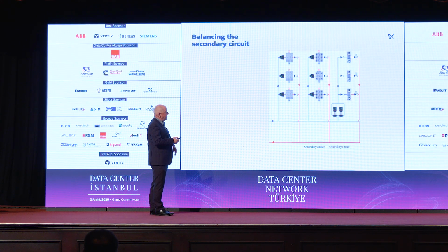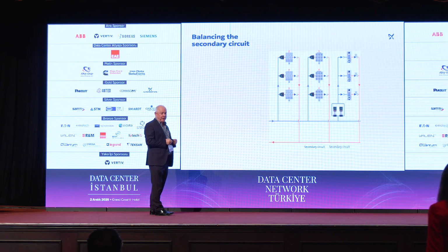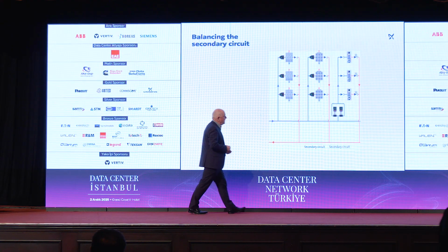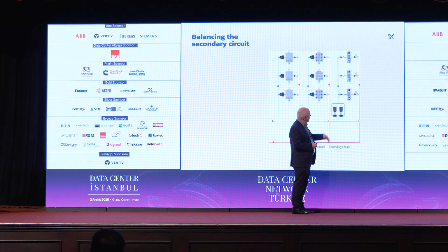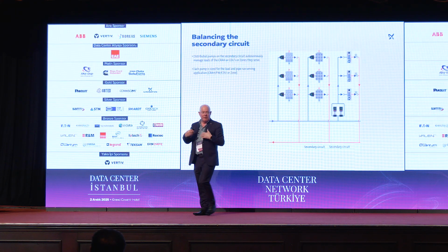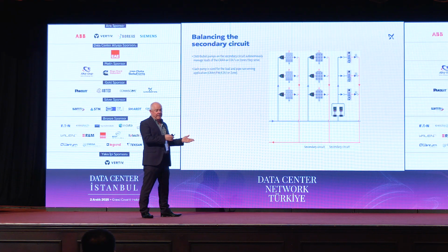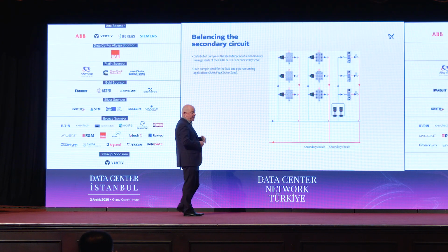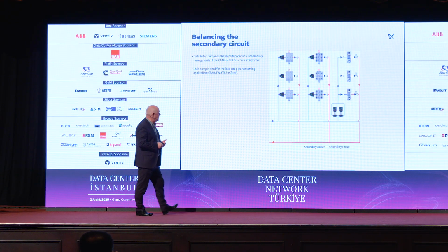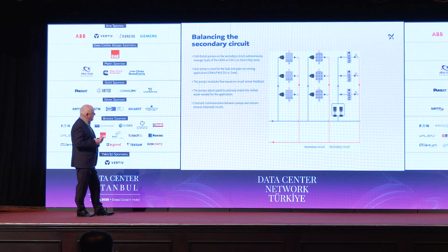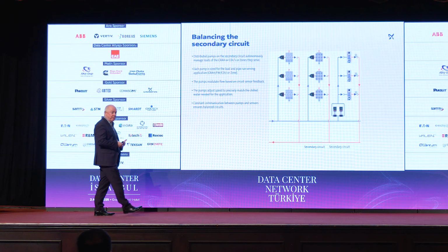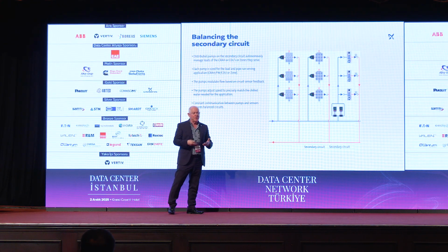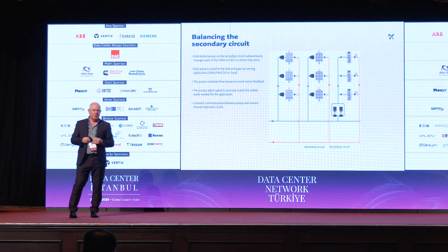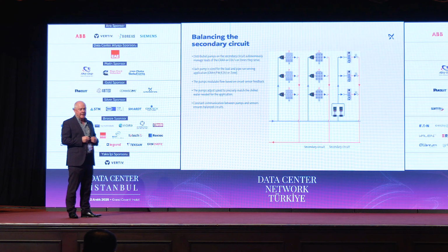So if we look at the secondary side, as I said, there's a pump on each load, which is providing the right amount of cooling. And we can see here where we've got a zoned load where we've got one pump pumping up to various different loads. And we can mix and match different kinds of cooling. So we can have fan walls, we can have CRAH units, we can have liquid cooling, all on the system. It doesn't really matter to the individual pumps what the load is. They're getting sensor feedback and they're reacting to what's going on. And we're constantly monitoring what's going on in the system and constantly reacting to any changes in that system. And that goes through the life of the whole pumping system. As we might get some build-up in some of the pipes or whatever, the pumps will see that and they will react in accordance with what's going on. So they're constantly looking at the load and meeting that demand.